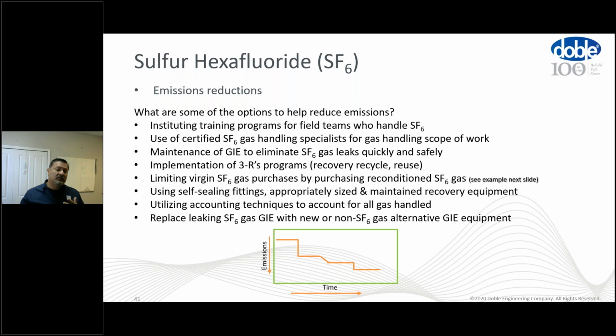If you use a piece of equipment that won't recover 100% of the gas, you think you've gotten as far as you can, but it really can't get to that blank off pressure, if you will. You're going to leave SF6 gas in the GIE. When you open a compartment, you're just creating a spill and you're introducing greenhouse gas into the atmosphere. Utilizing accounting techniques, you need to know what you've handled. How much gas have I recovered? Have I recovered 100% of this gas, or did I leave some in there? Really important to know, and that helps you understand where you stand as an organization.